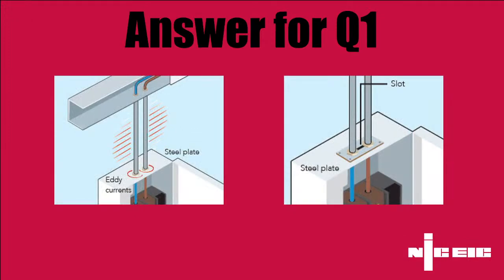Yeah, absolutely. So brass isn't ferromagnetic. The magnetic field generated by the conductors isn't going to create a field within that brass material because it's not ferromagnetic, so that's okay. And just showing some slides to show that if it were a steel enclosure, steel being ferromagnetic, it would need to be slotted to reduce the effect of those eddy currents that are created.